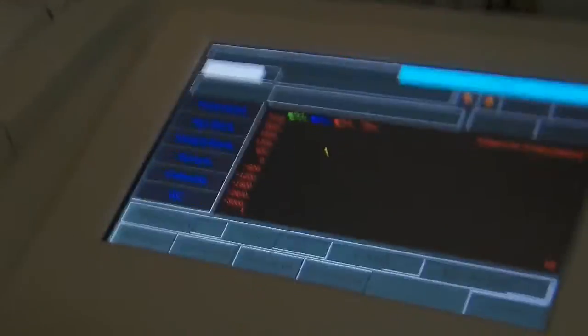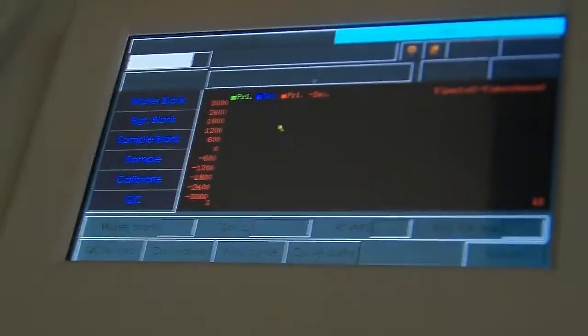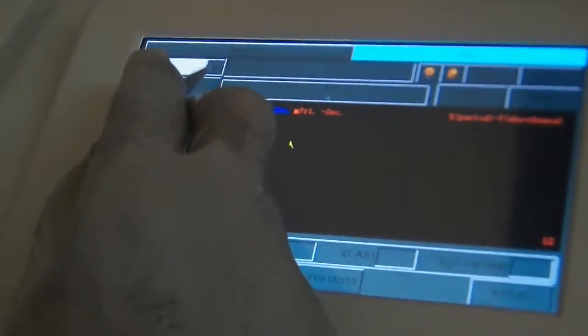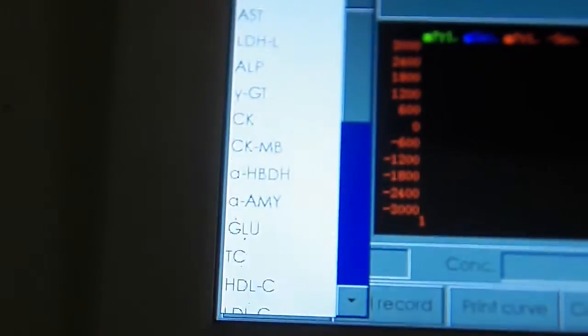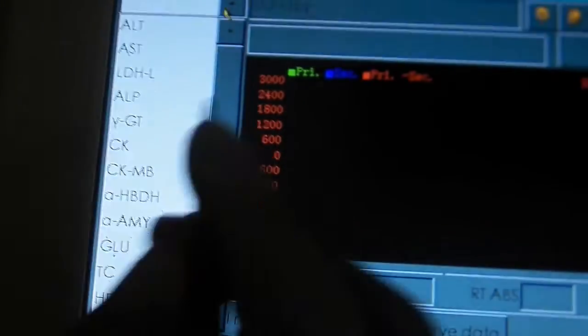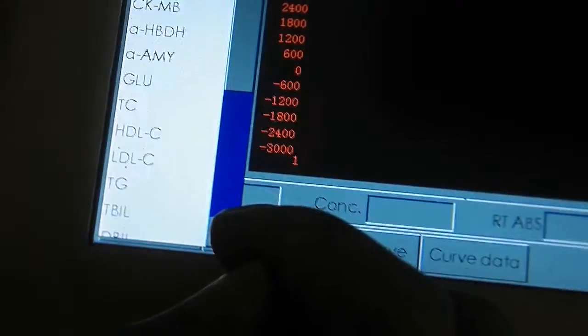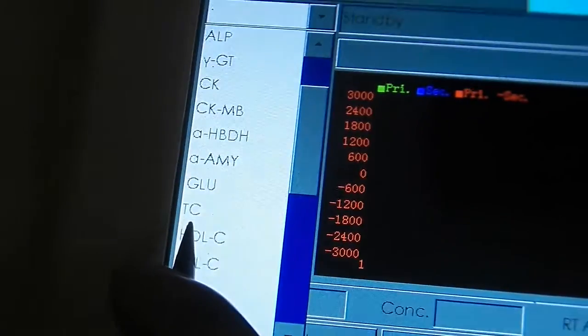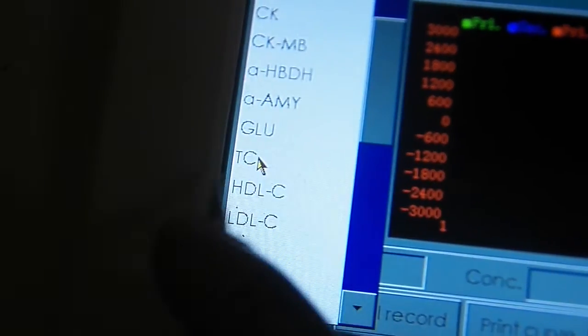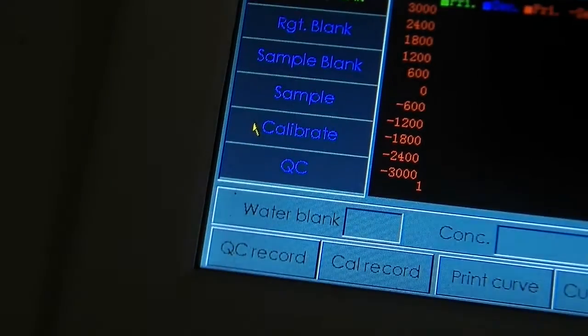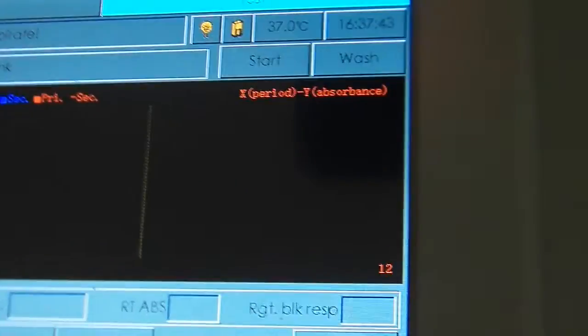So this is ready for testing. So how do you test? You come to the machine. You go to test. You select test. And then, first thing you have to do is you have to select the parameter that you're going to use. I don't know if you can get a clear view on that. So we're looking for total cholesterol. It is noted as TC on this machine. So we select TC.